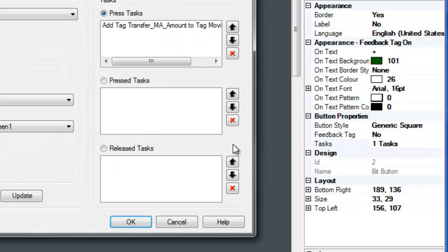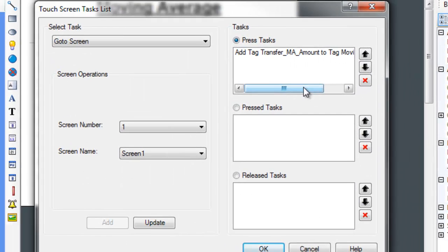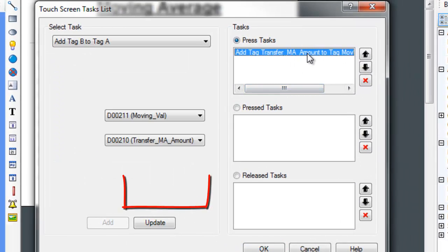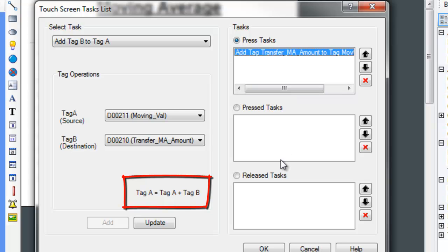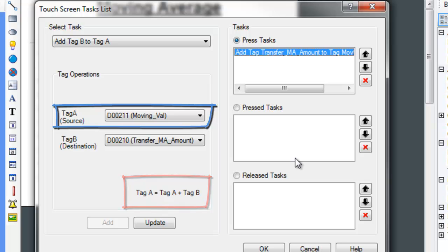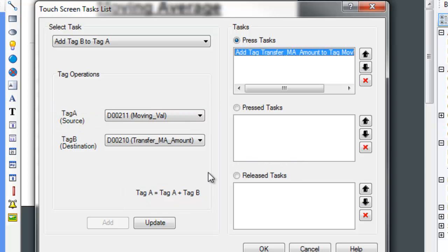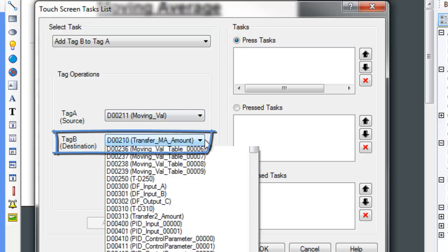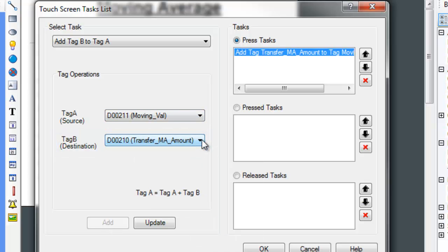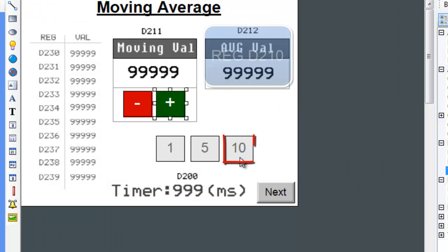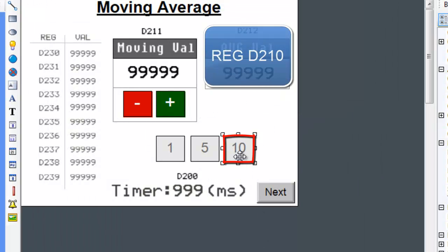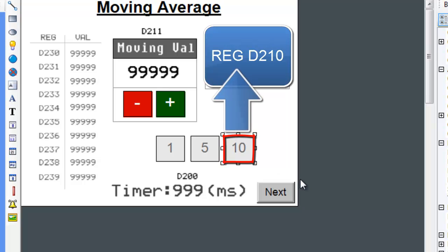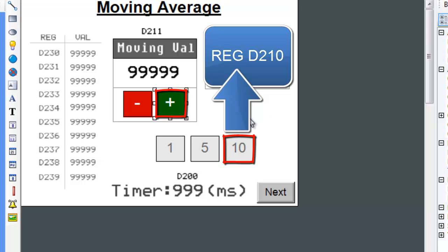As you can see, the tag operation is simply add tag A and tag B and store the value in tag A. In tag A, we have the moving value which is register D211. Tag B is Transfer_MA_Amount which is dictated by the radio buttons. So if the 10 button is pressed at that particular time, a Constant 10 is stored in register D210, and when we increment the moving value, it will increment by a factor of 10.